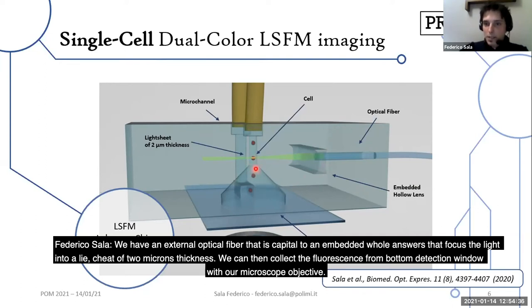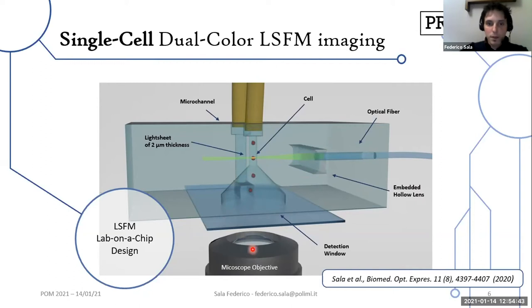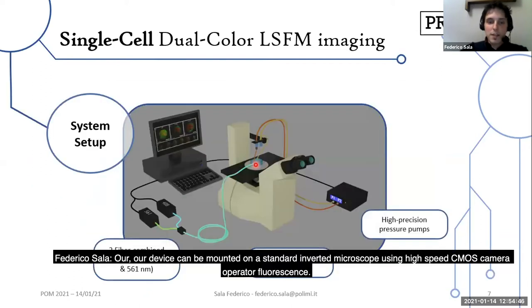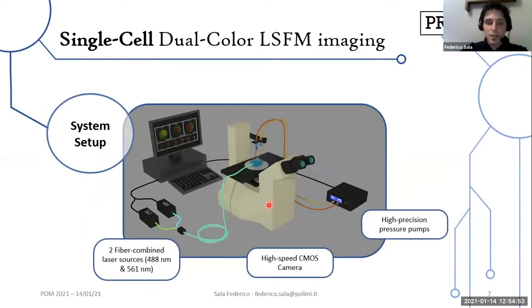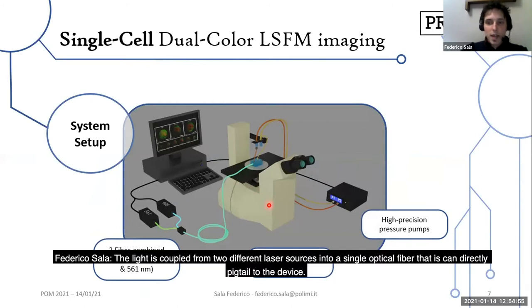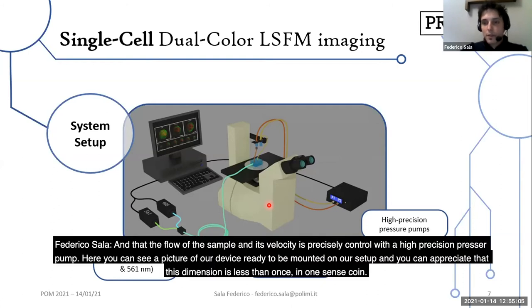We can then collect the fluorescence from a bottom detection window with our microscope objective. Our device can be mounted on a standard inverted microscope using a high-speed CMOS camera to acquire the fluorescence. The light is coupled from two different laser sources into a single optical fiber that is directly pigtailed to the device, and the flow of the sample and its velocity is precisely controlled with a high-precision pressure pump.